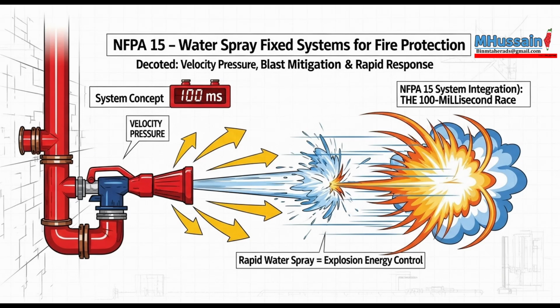Okay, imagine 3 adjacent systems, A, B, and C. System A is over a heat exchanger, B is over a pump pad, C is over a cooling tower. A fire starts at the pump pad under System B. Right. Now, the burning liquid from the pump fire, B, could flow beneath A and C. At the same time, the heat and hot gases rising from B could easily trigger the heat detectors in both A and C. So even though the fire started in B, the way the fire spreads, the liquid flow, the heat radiation, the hot gas movement, forces the engineer to calculate for all 3 systems, A, B, and C, running simultaneously. Yes, exactly. A.7.1.1.2 confirms this logic.